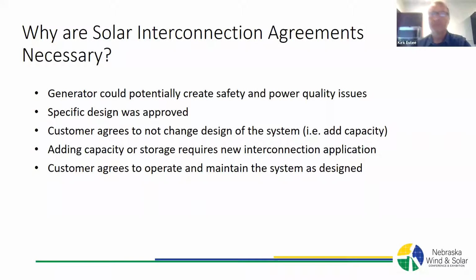It's important because a specific design was approved through the interconnection application process. The approval to construct wasn't approval to construct anything — it was based on the specific information in that application. Part of the agreement is that the customer agrees not to change the design over the years; you can't, for example, add capacity. If a customer wants to add capacity or storage, which is fairly common now, a new interconnection application needs to be filed so the additive impact to the grid in that area can be considered. The customer also agrees to operate and maintain the system as designed.